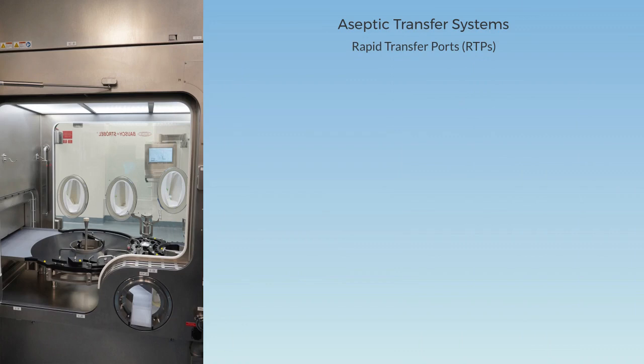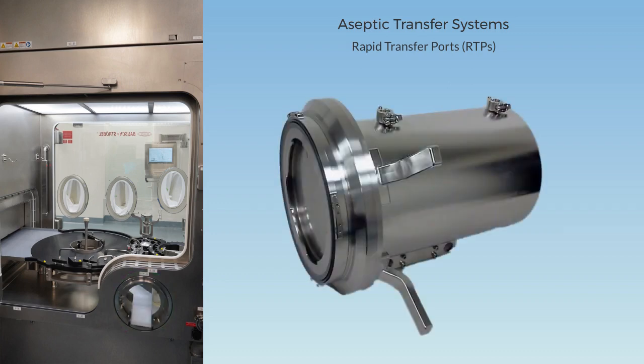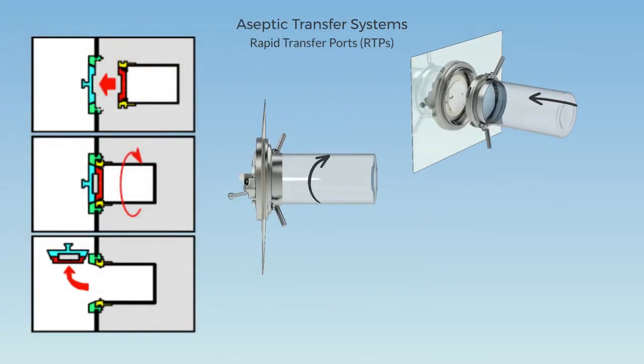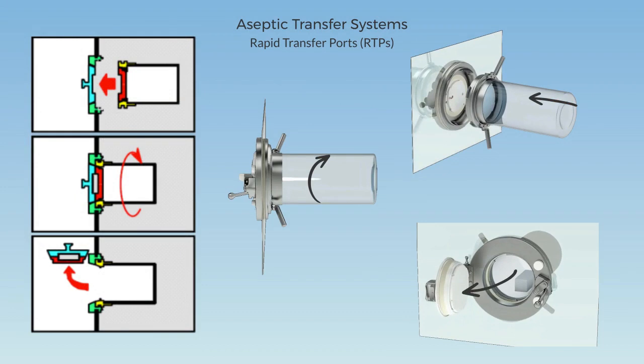The rapid transfer ports, RTPs, consist of two main components. The port assembly is mounted in the isolator wall, and the can assembly is mobile and used to transfer the materials. Each has a door, seal, and an interlock function. When the two assemblies are mated, equipment, waste, product, or materials can be rapidly transferred into and out of the isolator without breaking containment. The interlocks protect against the port door opening if the can assembly is not fully docked.